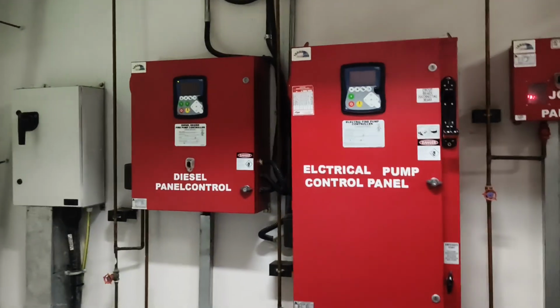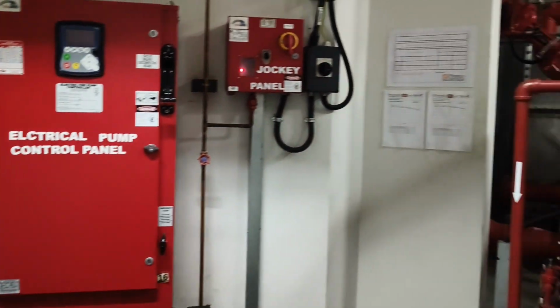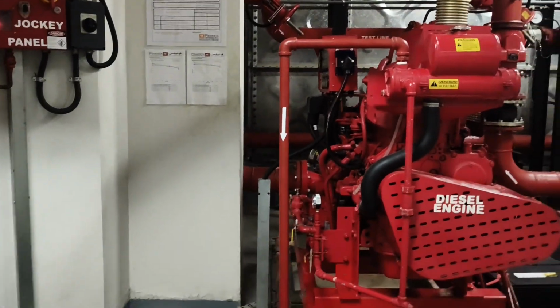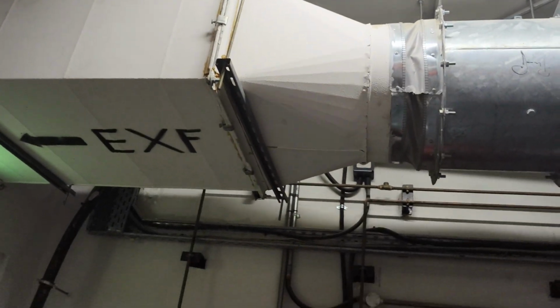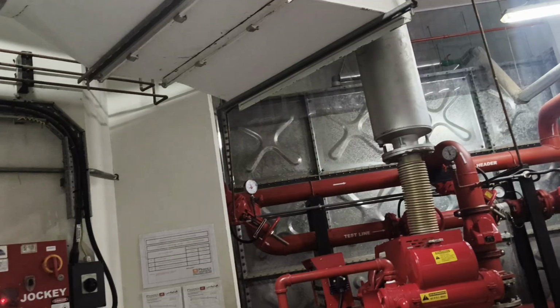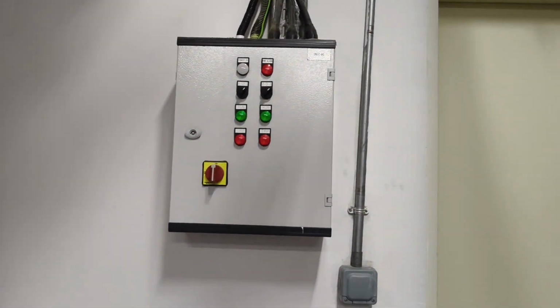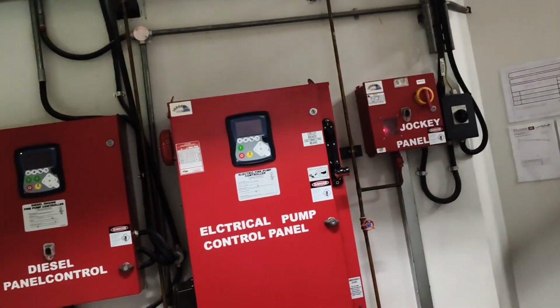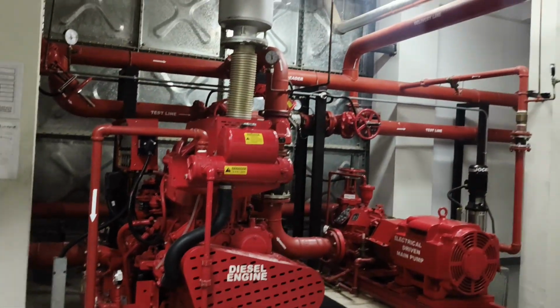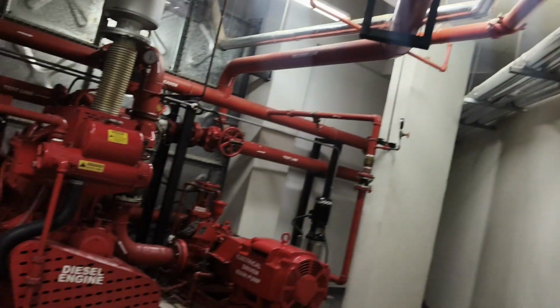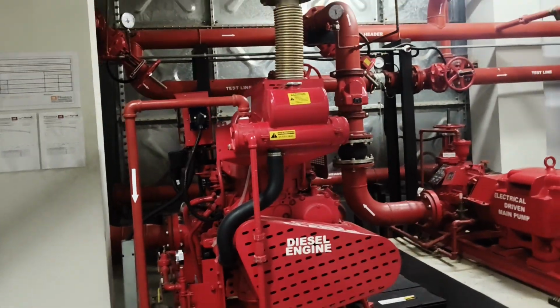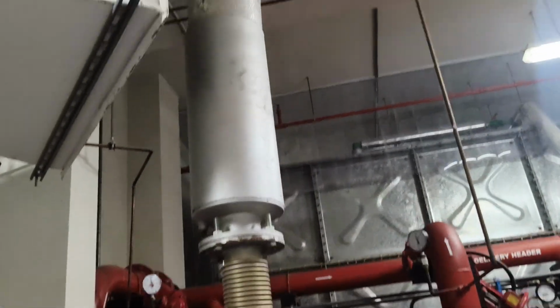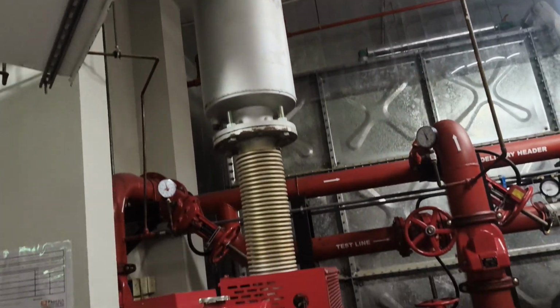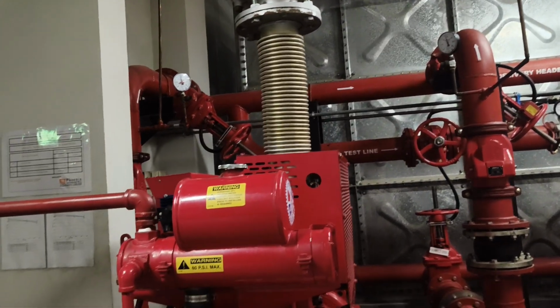That is why the battery calculations come in, as per how long it can stand to do the pressurization, or to hold the system in place in case. And here you can also see we have an exhaust fan which is connected to the diesel as well. So immediately the diesel runs, the exhaust fan which has been connected here is going to also run to keep the room conducive, because this actually brings heat whenever it runs. And mainly, this is supposed to be cladded, like what has been done up there. So we will request for cladding, to reduce the heat that is inside the room.